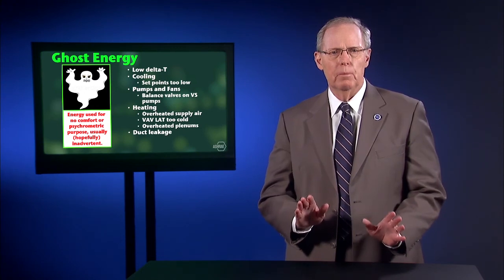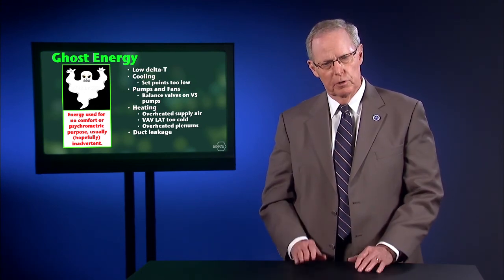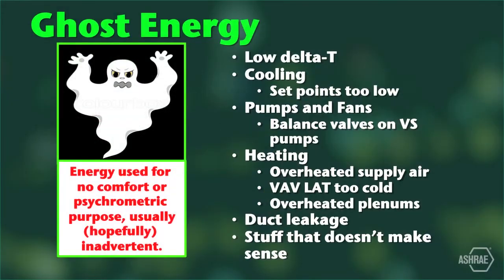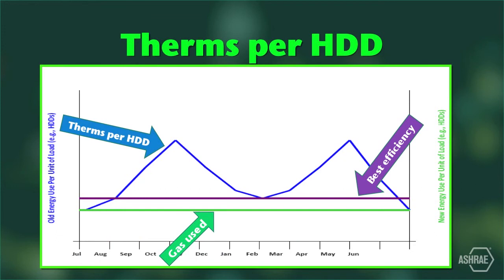Now, throughout the webinar, you're getting a good dose of Durkinisms. Here's another one. When you see stuff that doesn't make sense, chances are it doesn't make sense. Here's an example. Get your heating bills and graph the month-by-month therms per heating degree day with the winter months in the middle of the x-axis. Many, maybe most, will look like the blue line. Now, how much sense does it make that the gas use per heating degree day is significantly more in October and May than it is in January and February?